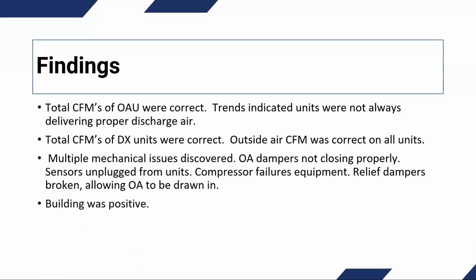The building, fortunately, was positive, so we didn't have a problem with the building being positive. And during our thermal scans, we did indicate that there's possible envelope issues with the building. Nothing major, but we did identify some areas of concern. Of course, we always want our buildings positive, but moisture migrates. You don't have to have a negative building to have a humid building if you've got a really bad envelope, because moisture is going to migrate, and if you don't have a good building envelope, you will still have problems even if the building's positive.